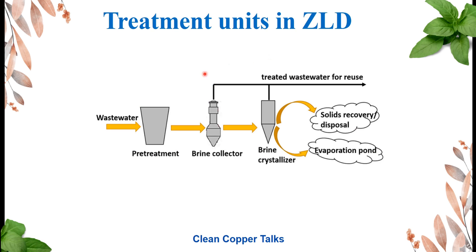In a ZLD system there can be two types of processes: thermal or membrane-based. In a typical thermal-based ZLD schematic, the pre-treatment step involves pH adjustment, de-aeration, or softening to make the wastewater suitable for the next step. The brine concentrator uses thermal techniques such as mechanical vapor compression to extract pure water for reuse while concentrating the wastewater. This concentrated brine then goes to a brine crystallizer, which removes further water leaving behind solid, powder, or semi-solid waste.